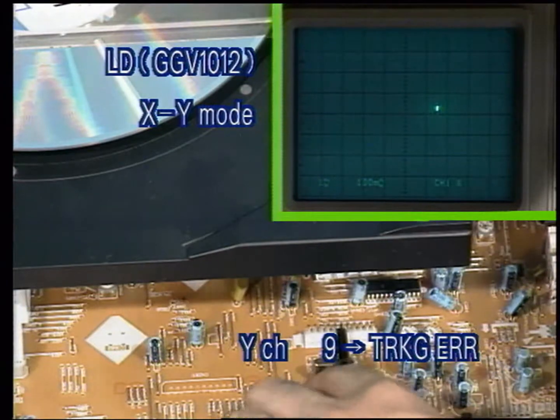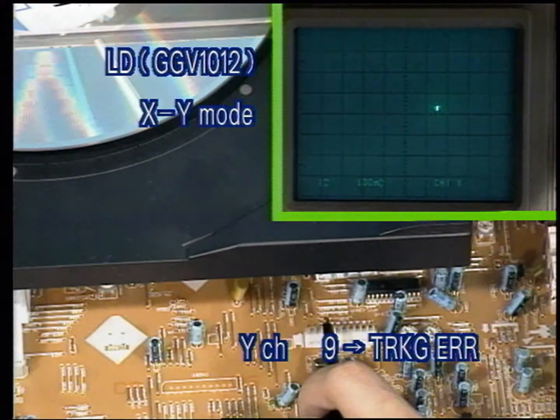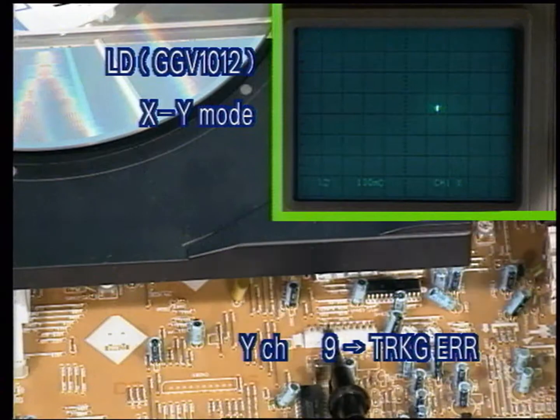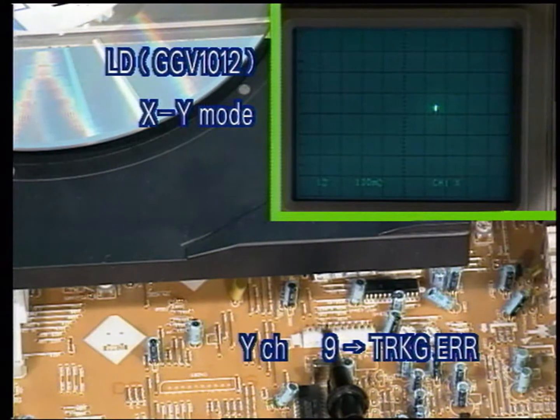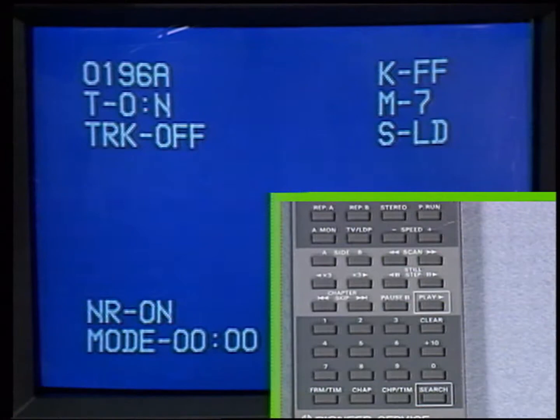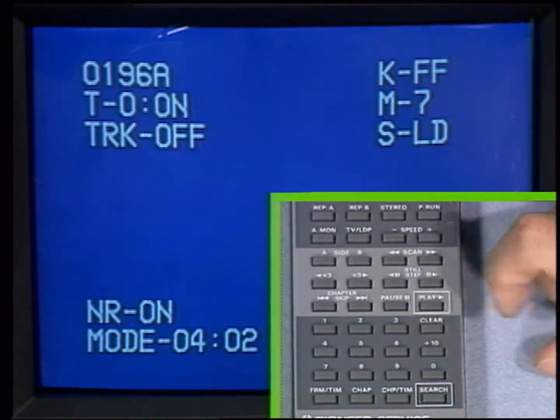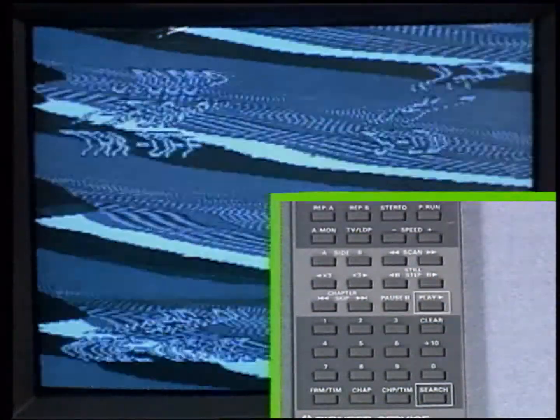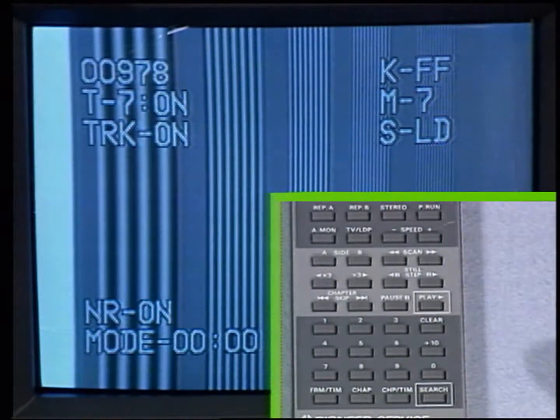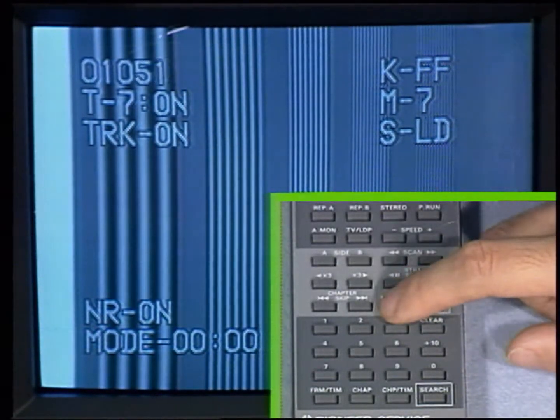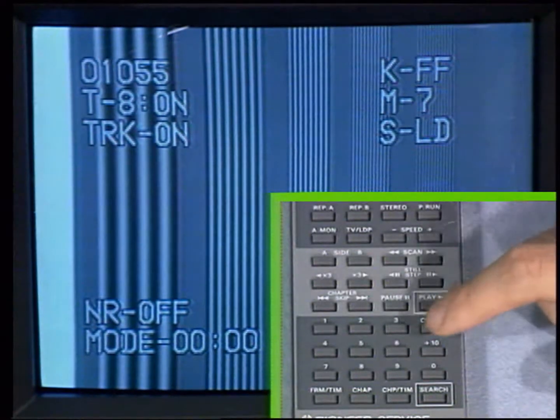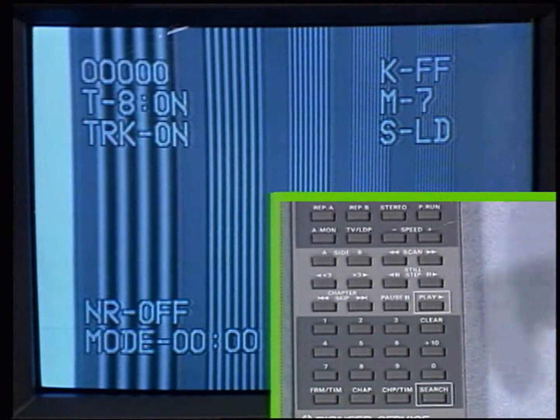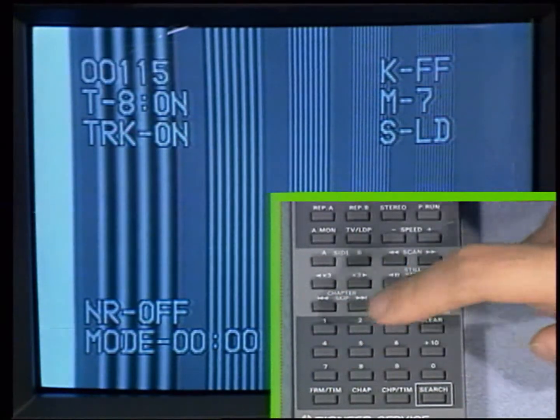In the XY mode of the scope, hook up the scope to TP9, which is tracking error, and load the LD test disc in. With the multi-speed plus key, turn the tilt servo on. With the play key, start playing with the tracking servo open. With the play key pressed once again, close the tracking servo loop. With the pause key, freeze the picture. With the plus 10 key, prepare for the search and enter the frame number 115. Then press the play key to make a search.